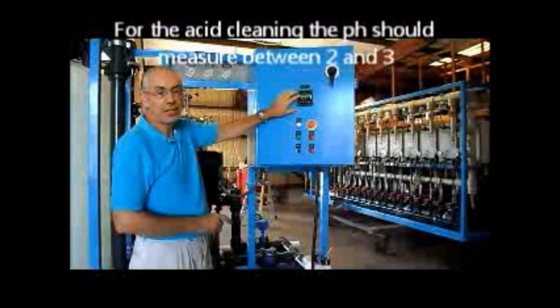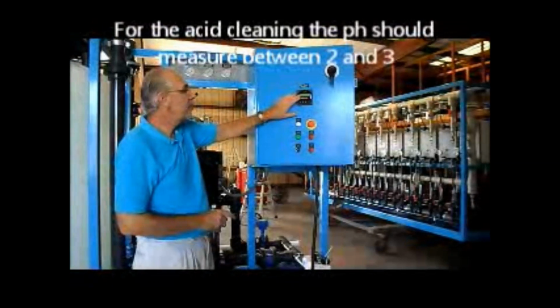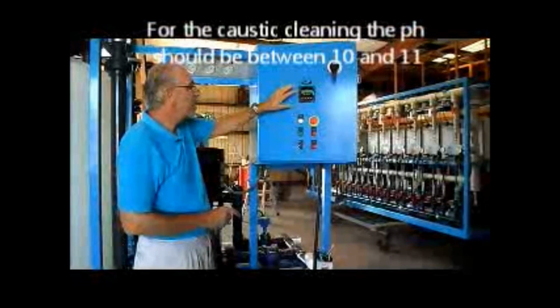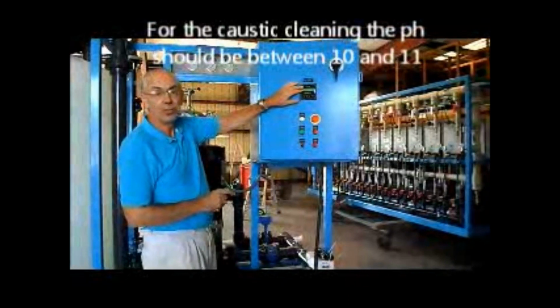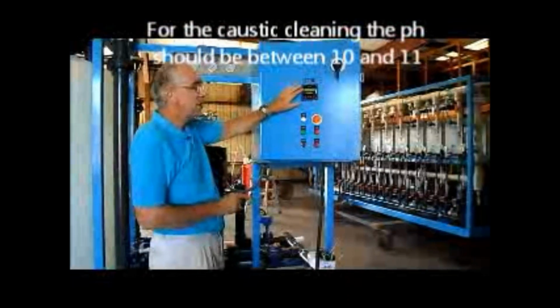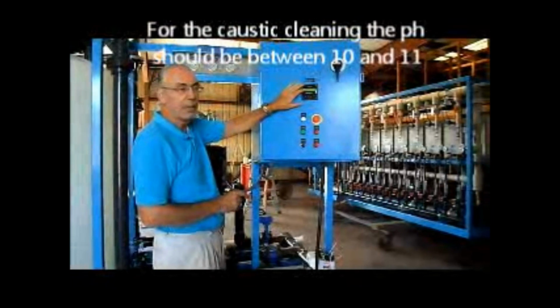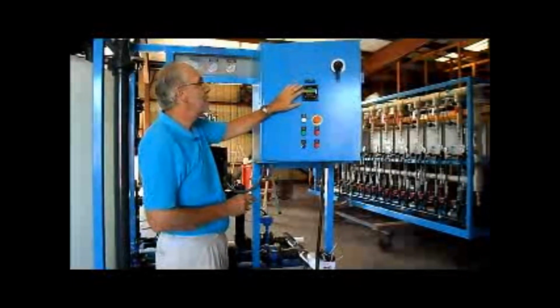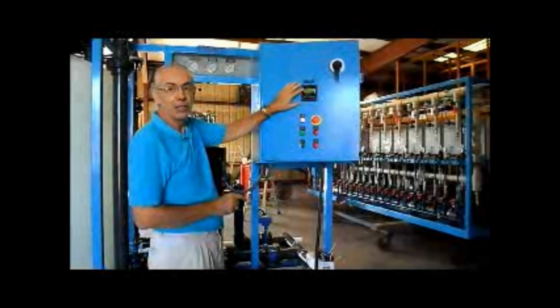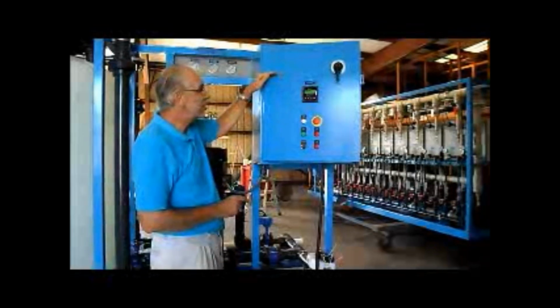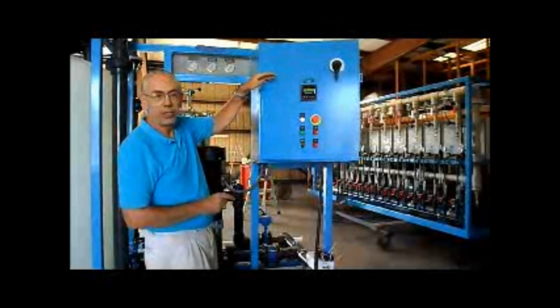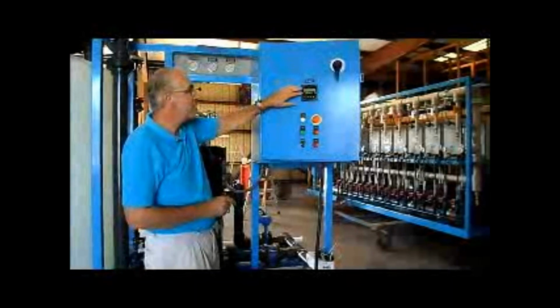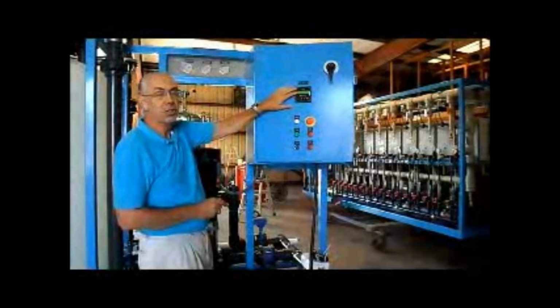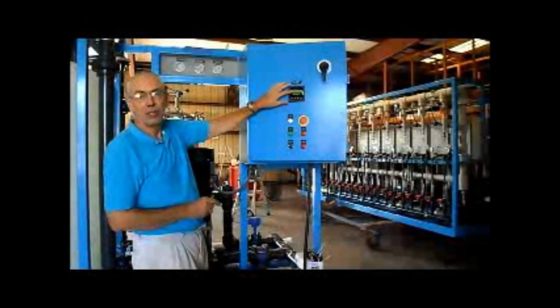If you're doing a caustic cleaning with high pH, it should be between 10 and 11. These are approximate numbers and depend on the cleaning solution you use. In general, if you're going to remove mineral scale, calcium, magnesium, things like that, acid clean, low pH 2 to 3. You're going to take out bacteria, silica, colloids, silt, sediment, use a high pH solution. pH here should be 10 to 11.